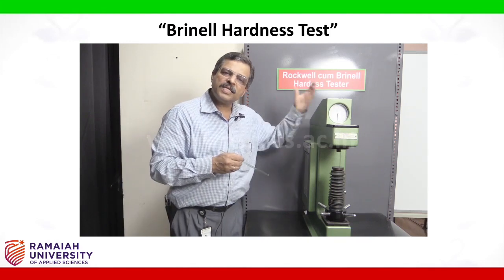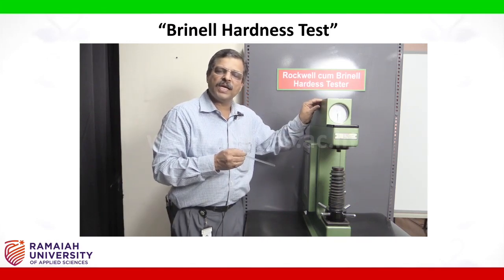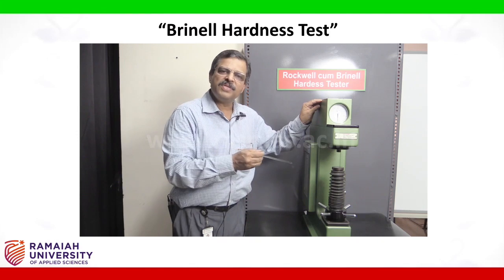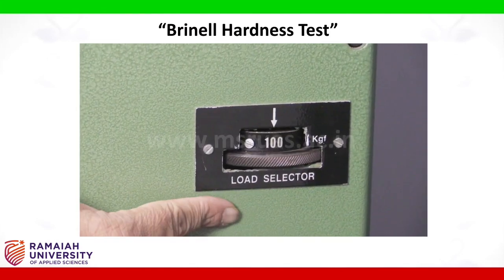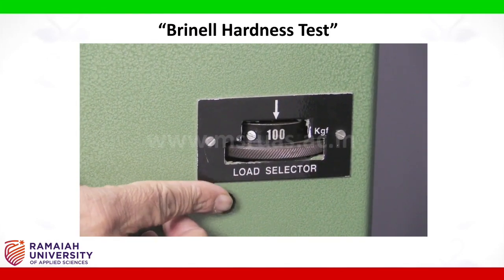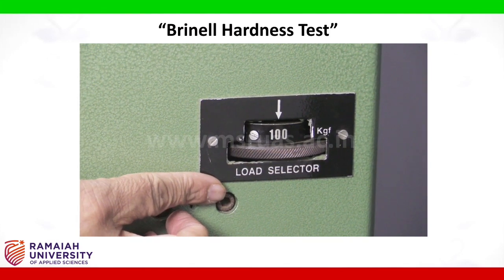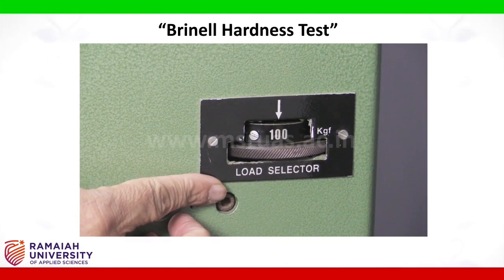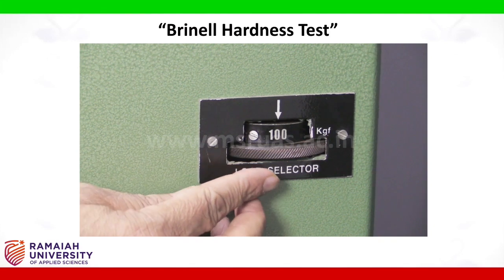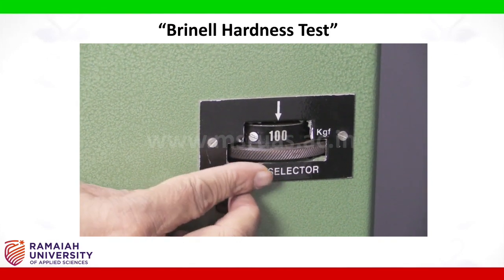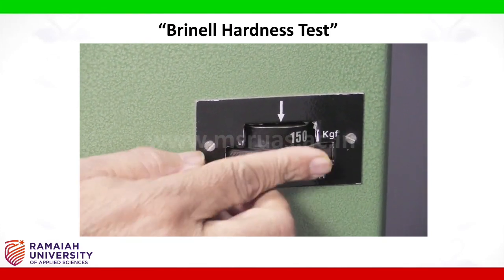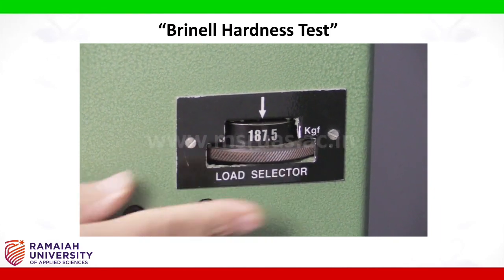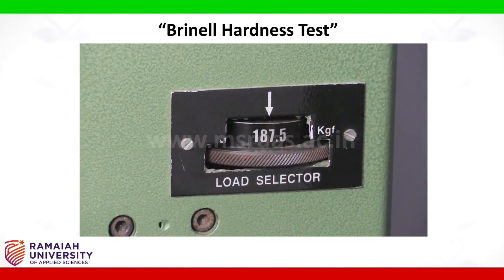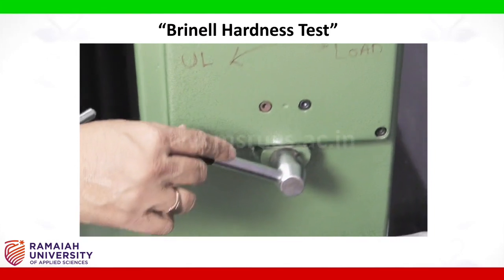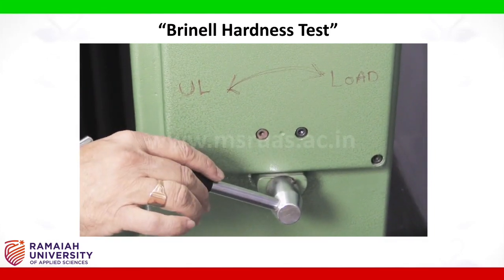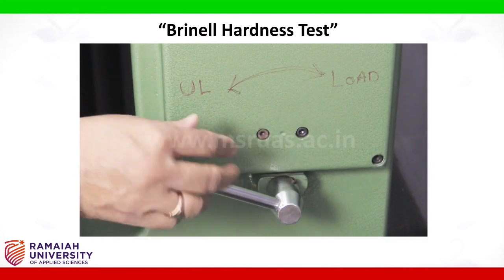Now on the other side of the machine we have the load selector and the levers. We will see that now. This is the load selector. Depending on the type of material for which the hardness is to be found, we can select loads. In this machine there are loads which we can select from 100, 150 and 187.5 kgs. Now we will move to the load selector. This lever helps us to apply load and remove the load.